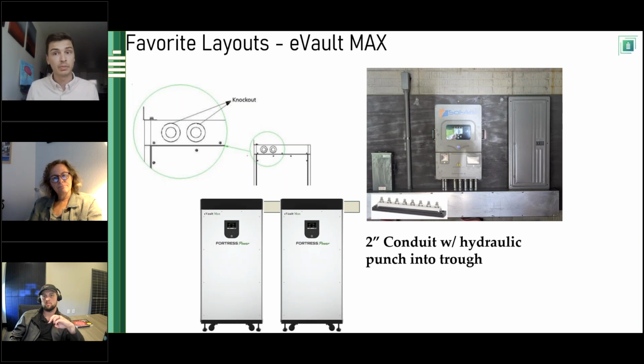There are many ways you can do busing. We always recommend that if you have a project with 2 or more Evault Maxes, you do a bus bar. A one-to-one with, say, a Sol-Ark or an NV, you can just go right from the hybrid inverter down to the battery—no fuss, no muss. As you get into larger systems, you want a way to balance the power coming from all these batteries onto a bus bar.